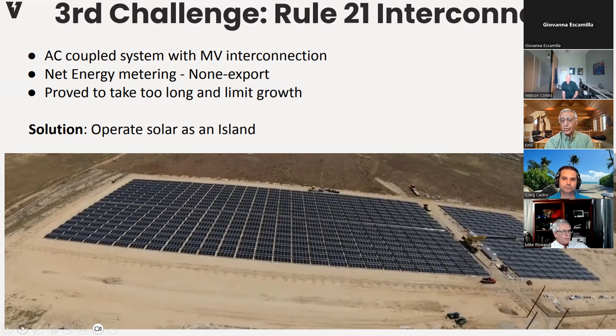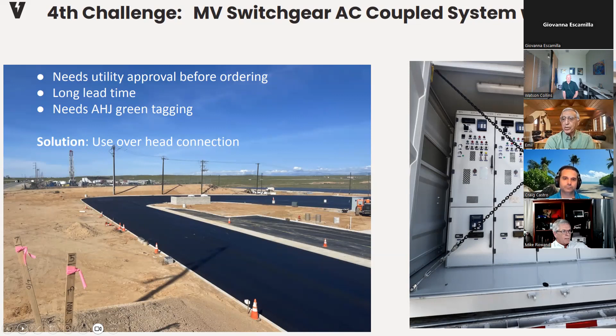Having selected medium voltage as the base facility to interconnect with PG&E, that presented a new challenge: we needed a medium voltage switchgear with an incoming section, a metering section at medium voltage with CTs, and vacuum breakers. We ran into huge supply chain challenges getting that switchgear on a timely basis. Eventually, PG&E helped guide us to an alternate solution using an overhead connection, which reduced both cost and time to get the medium voltage connection.